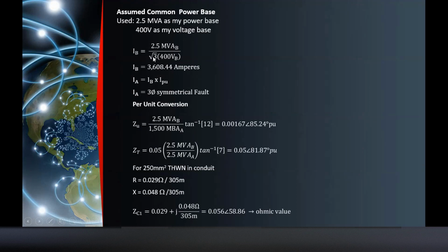Therefore, since I declared a power base and voltage base, what will I get? I base, right? I base is simply the 2.5 MVA base divided by square root of 3 multiplied by your voltage base, which is 400 volts. So I will get 3,608.44 amperes. The 3,608.44 amperes is the same as the secondary full load current of the 2.5 MVA transformer. Earlier, the formula I asked you to remember: I per unit is equal to I actual divided by I base. I just rearranged the formula: I actual is equal to I base times I per unit, where I actual is my three-phase symmetrical fault.